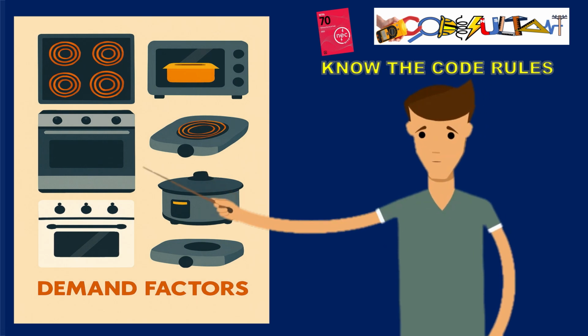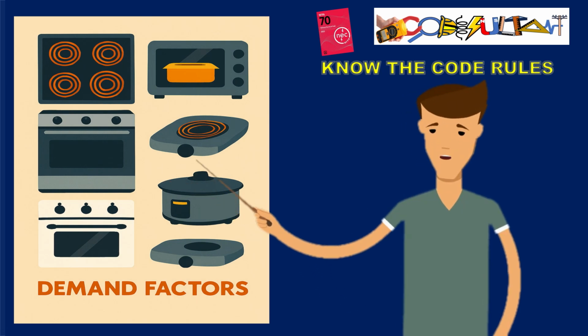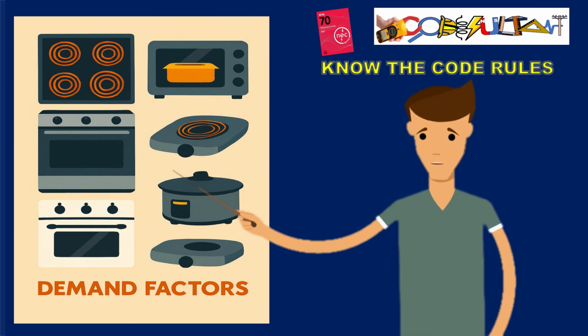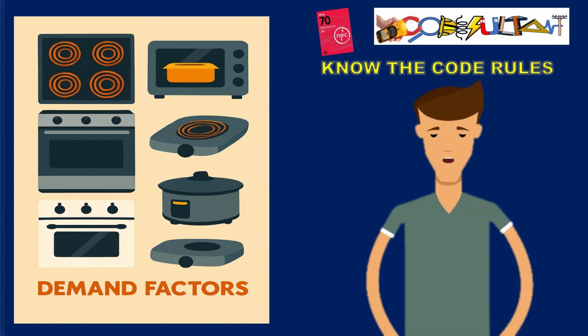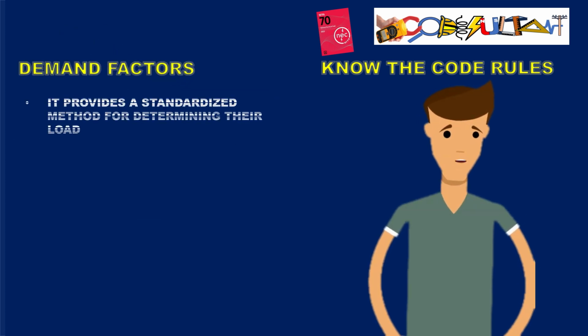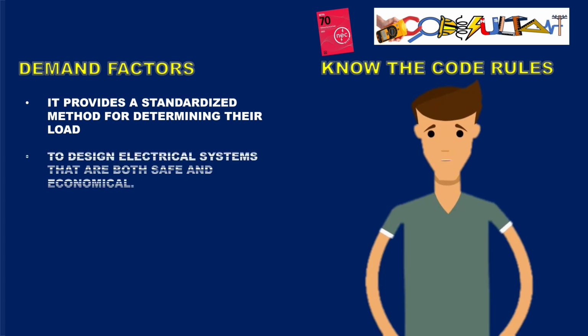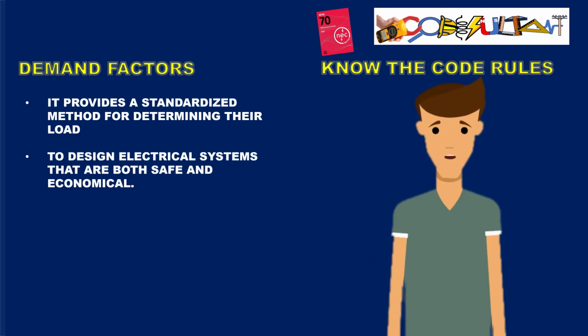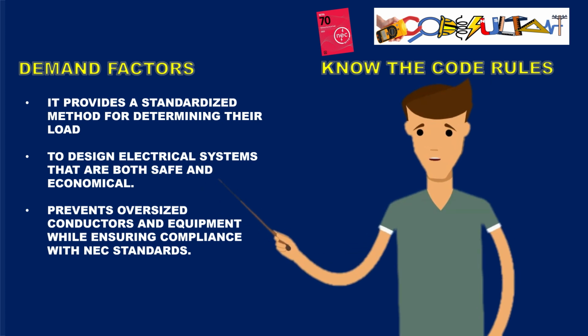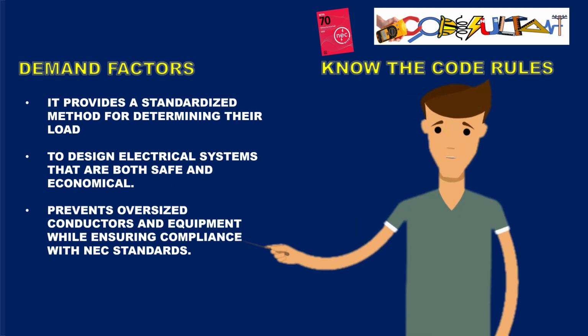This table is specifically about demand factors for cooking equipment, household electric ranges, wall-mounted ovens, counter-mounted cooking units, and similar appliances. By applying demand factors, it provides a standardized method for determining their load, allowing us to design electrical systems that are both safe and economical. This prevents oversized conductors and equipment while ensuring compliance with NEC standards.